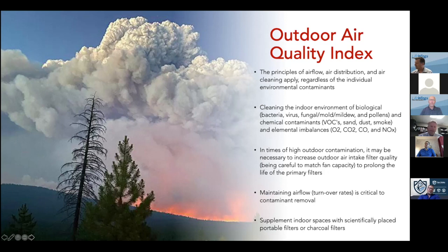I've actually had experience with wildfire smoke and outdoor wood boilers at several school districts, where we've had to go in and put charcoal air filters at certain times to remove the smell from the smoke. They were very successful, putting in a separate charcoal filter rack and using those charcoal filters when needed. So it is able to capture it.